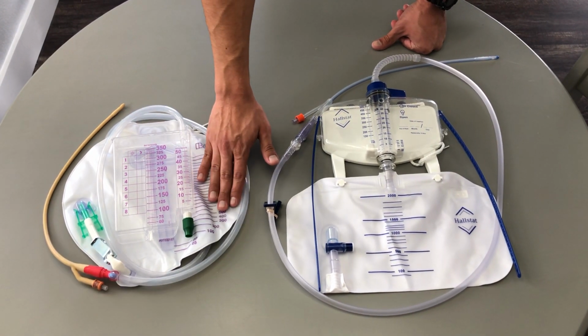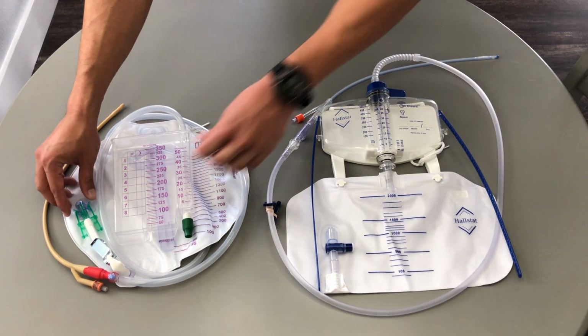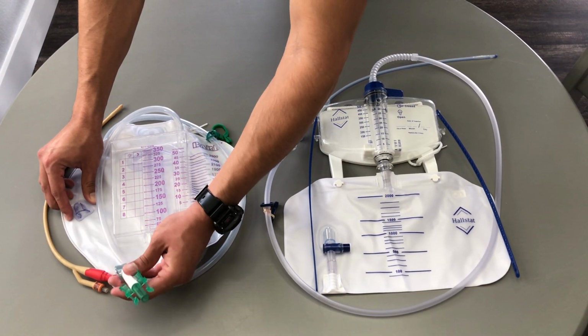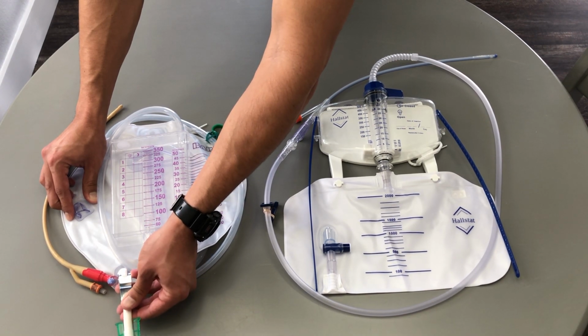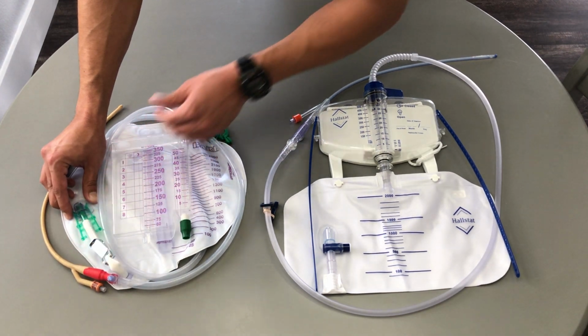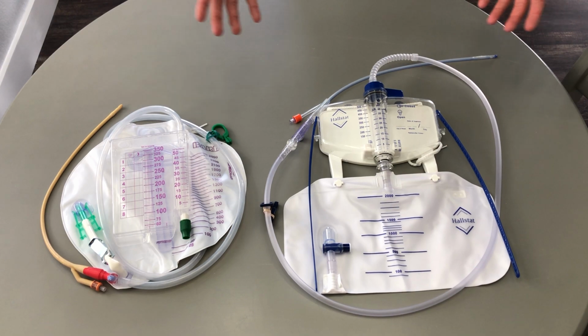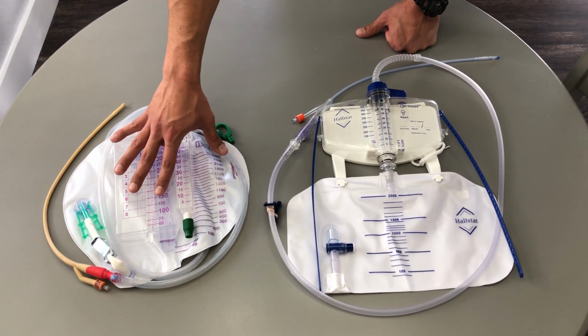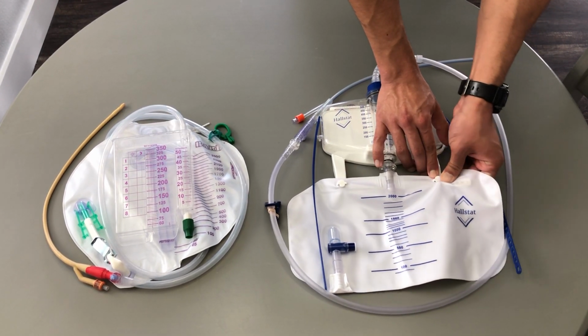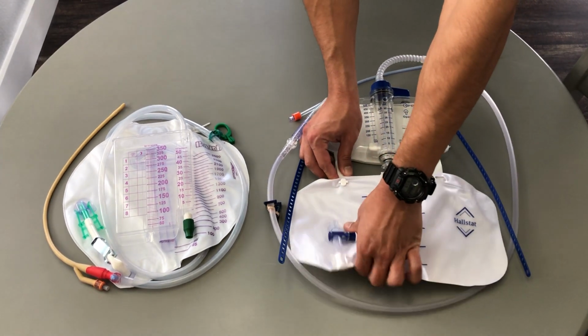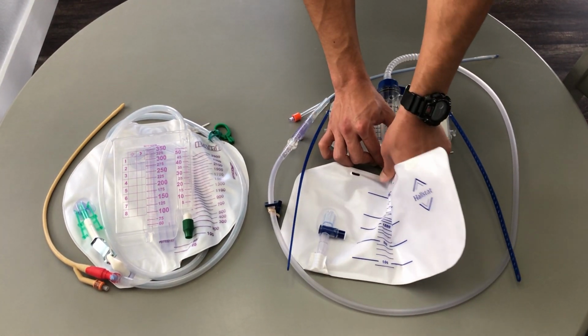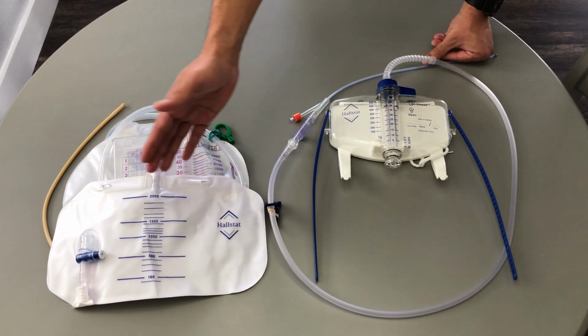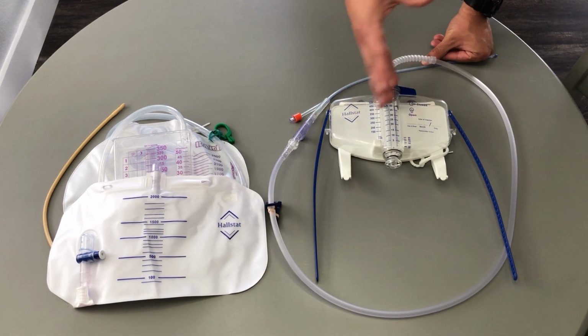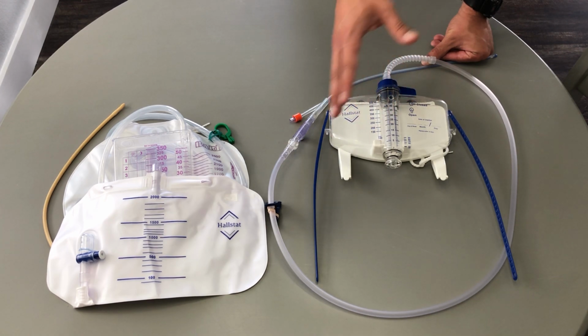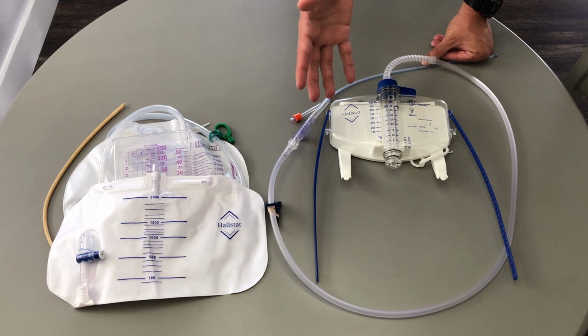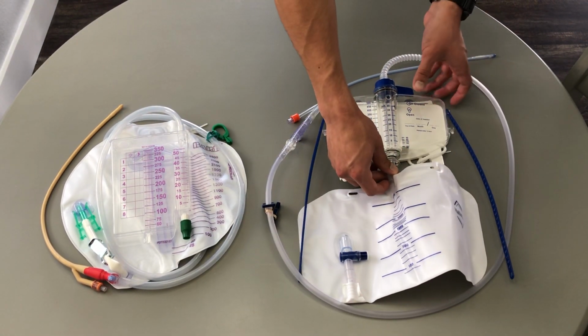In the Bard system, once the larger bag is full, or at the end of the day when you need to drain the bag, you have to open the bottom, release this port, and drain the urine into a dirty container. So it is a very unclean process where urine spills. It could get on the nurse, it gets on the floor, on the bed, and it does not promote a closed system. In the Hallstat drainage system, this bag can be disconnected at the end of the day and thrown away. And then a new sterile bag is introduced into the urine meter, and we have a new sterile bag every 12 hours, promoting a much cleaner system, a much cleaner way to dispose of the urine for the nurse, and a way in which it doesn't pour or spill urine anywhere into the hospital, which increases bacterial growth and general infection.